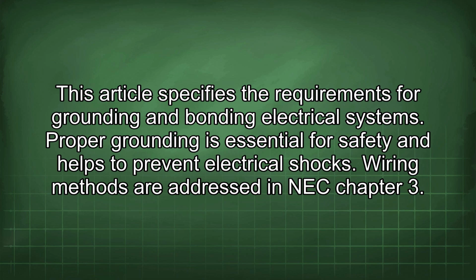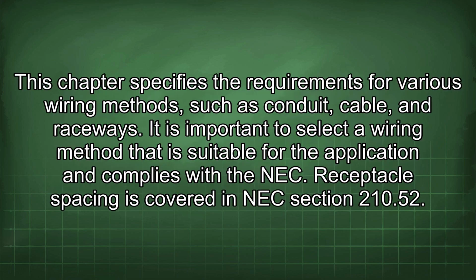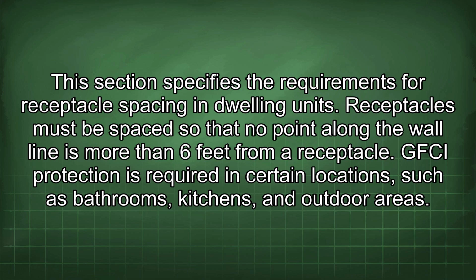Wiring methods are addressed in NEC Chapter 3. This chapter specifies the requirements for various wiring methods, such as conduit, cable, and raceways. It is important to select a wiring method that is suitable for the application and complies with the NEC. Receptacle spacing is covered in NEC Section 210.52. This section specifies the requirements for receptacle spacing in dwelling units. Receptacles must be spaced so that no point along the wall line is more than 6 feet from a receptacle.